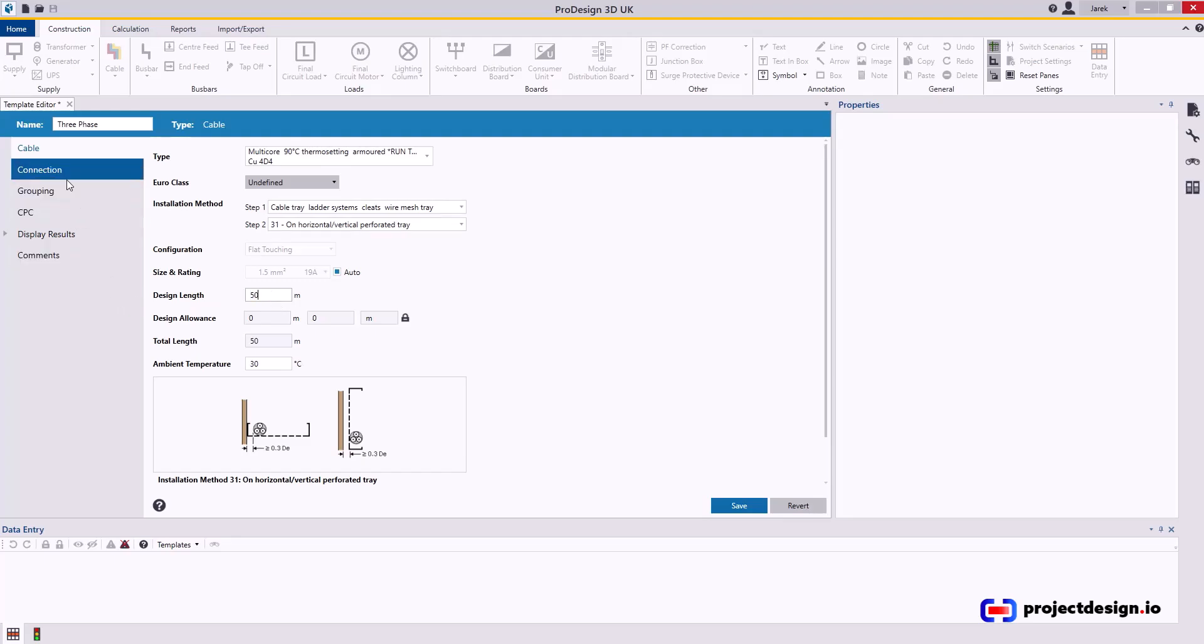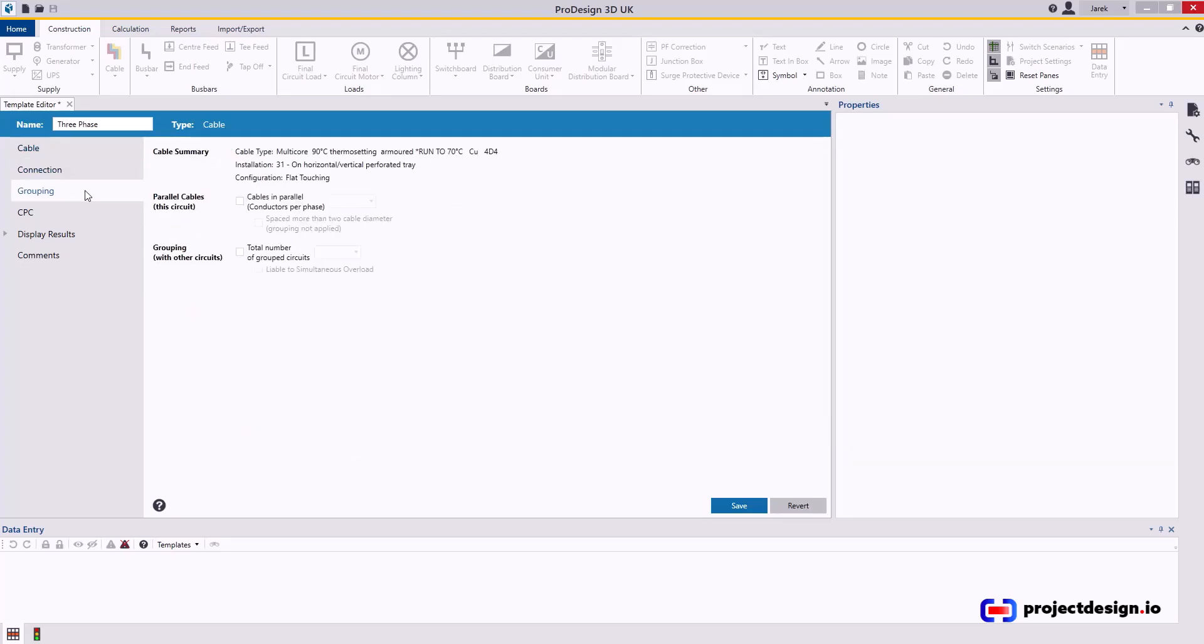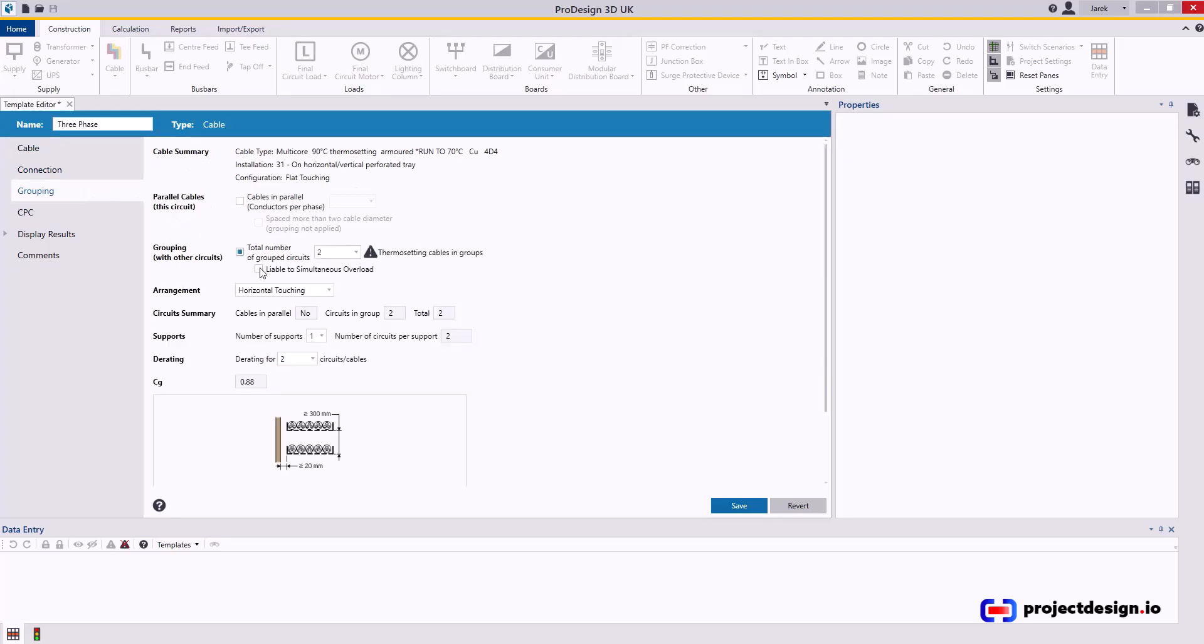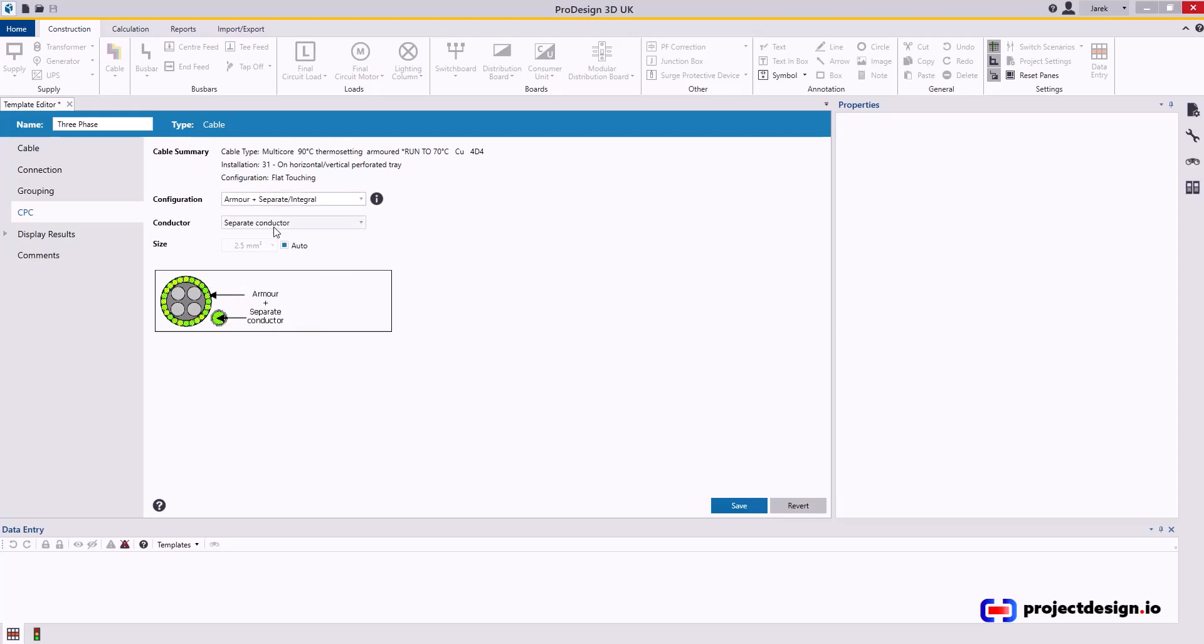Connection, that's three phase grouping. Again, it will be grouped always, right? Let's say again five circuits. CPC, well my preference is to run five core cables, so I'm going to select armor plus separate integral, because armor we always connect banjos and so on. It does form earth path and I'll go integral. That will create five core cable for me.